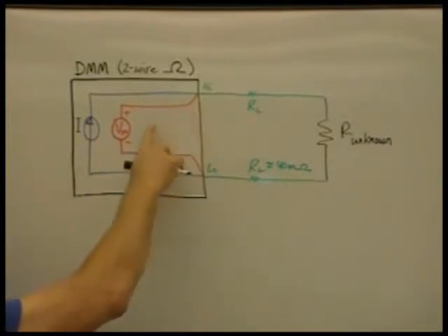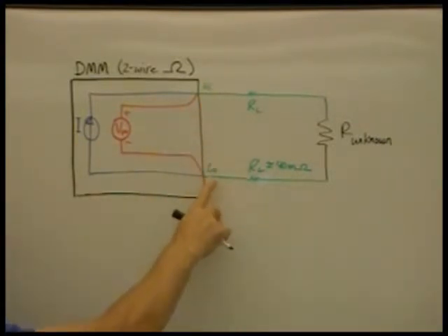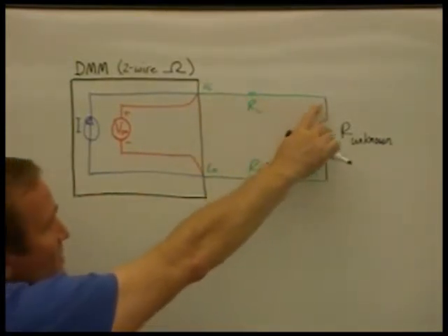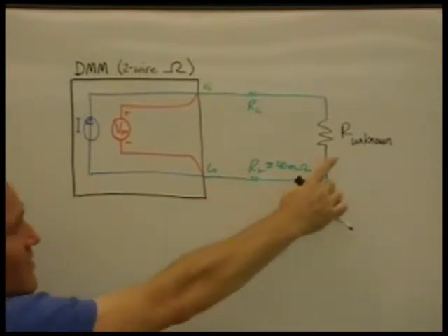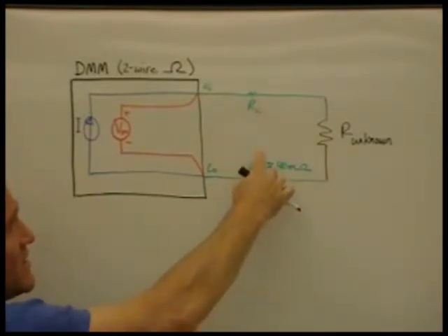And then we use the internal voltmeter to measure the voltage across the high and the low terminals. And therefore, we can calculate the total resistance in this path, the unknown resistor, as well as any lead resistance.